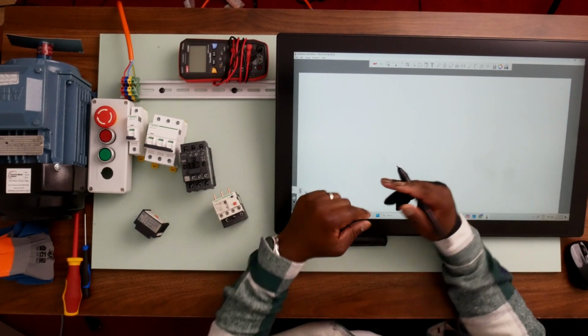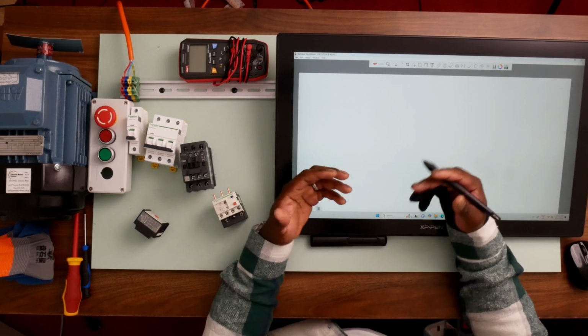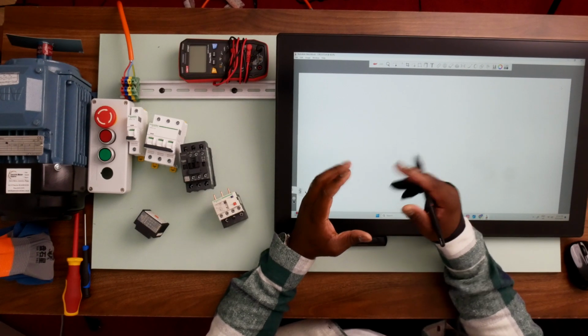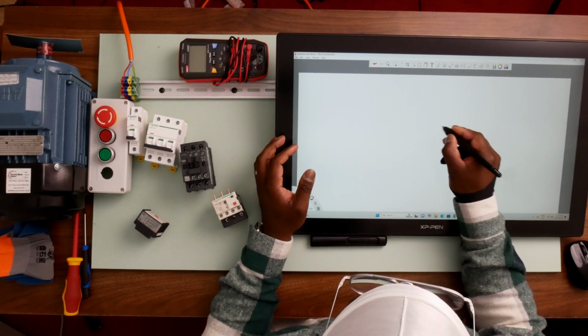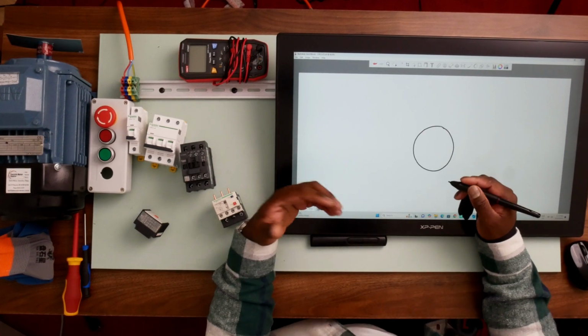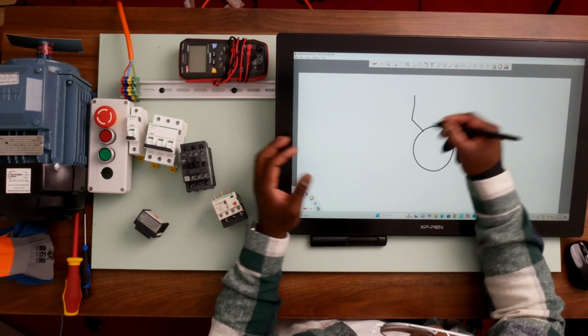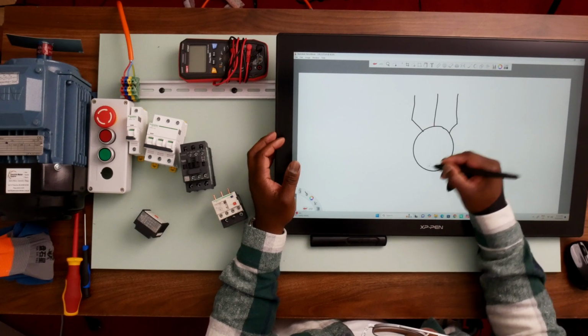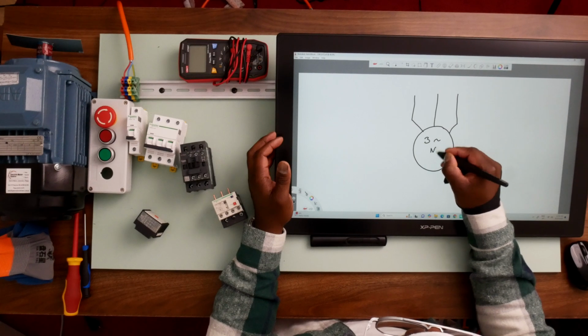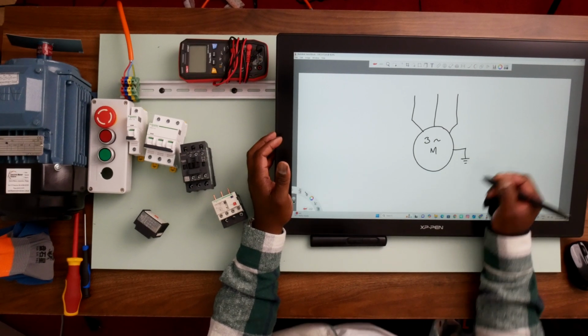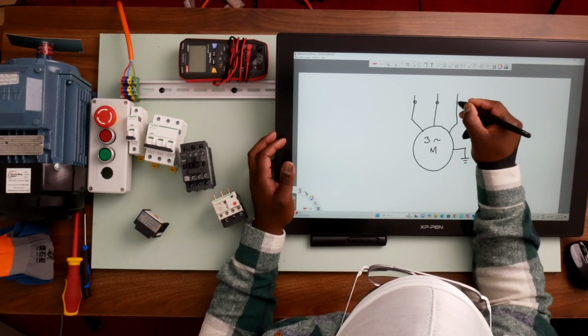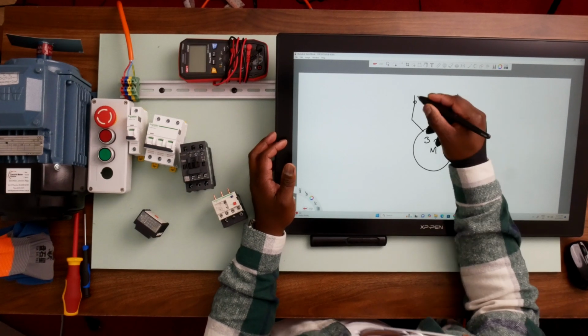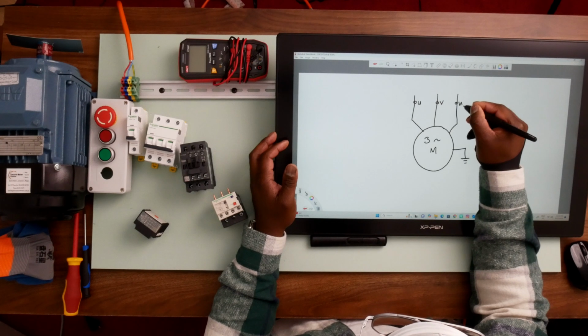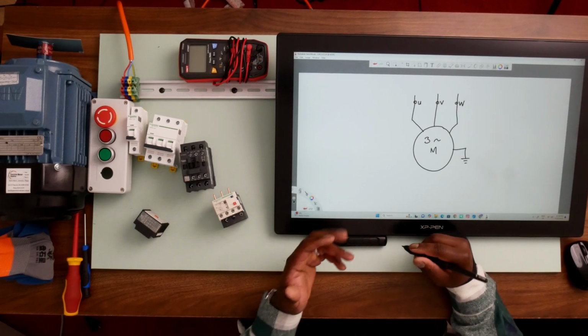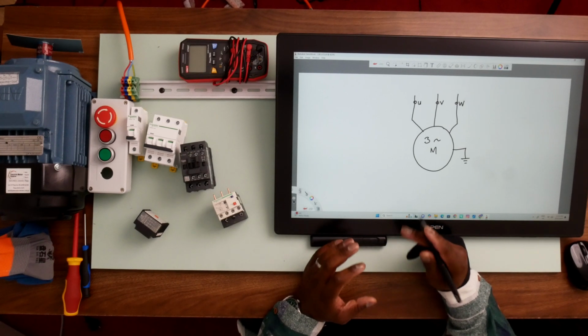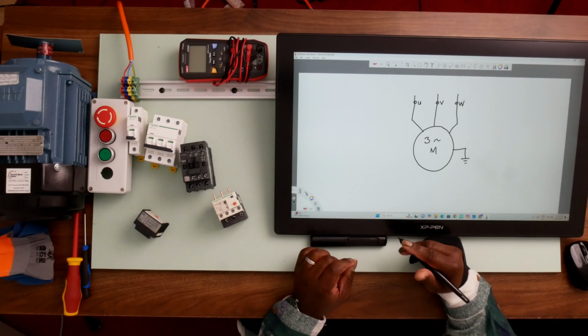Now the next component as we round up the power circuit is the electric motor. The electric motor is quite simple, but we can just draw the symbol to make sure that we are on the same page. So an electric motor is simply a circle like this. If it's a three-phase motor, we draw 3 wires going to the electric motor, and normally we draw them like this. Some will write M or 3-phase motor, and you might decide to show the earth connection here. Sometimes others will also show the terminal connections as well, which are normally U, V, and W. And as we proceed, you'll realize that when you do star delta circuits, you are going to require both ends of your windings. So you're going to require 6 connections to the electric motor.